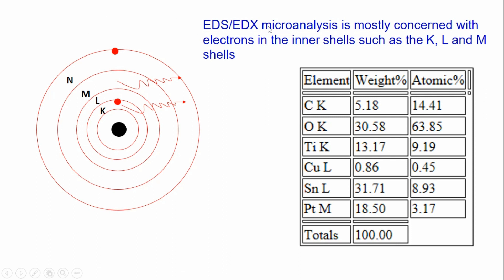EDS and EDX microanalysis is mostly concerned with electrons in the inner shells such as K, L, and M. In most cases you will see only these three shells. This is because we need the electron to go inside the atom and remove an electron from the inner shell, not the outer shell, because we need to know the elemental composition — and from there we can get information about how many elements are present.